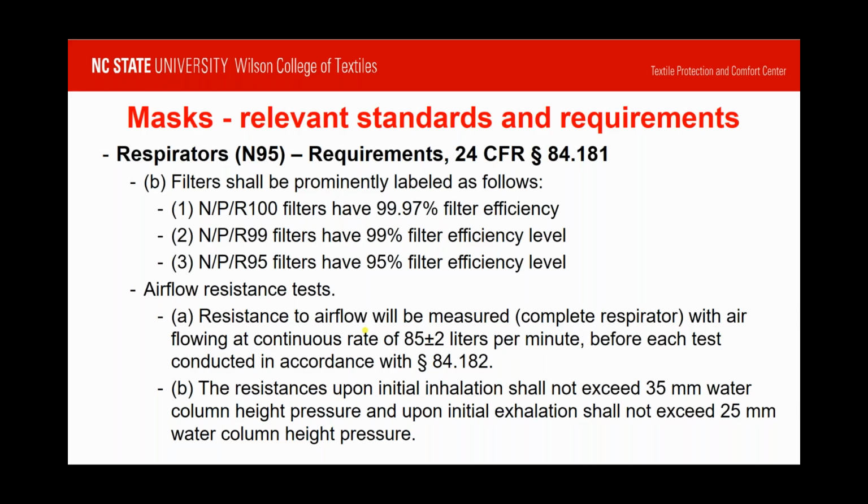They are different from the standard ASTM, EN, and ISO tests that are currently done. It is possible to translate these numbers back and forth, but the test is pretty much done on the complete respirator with an airflow of 85 liters per minute.